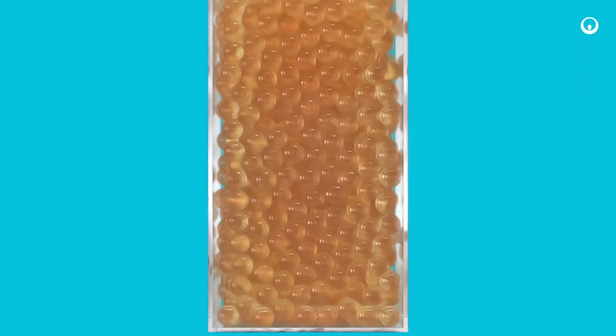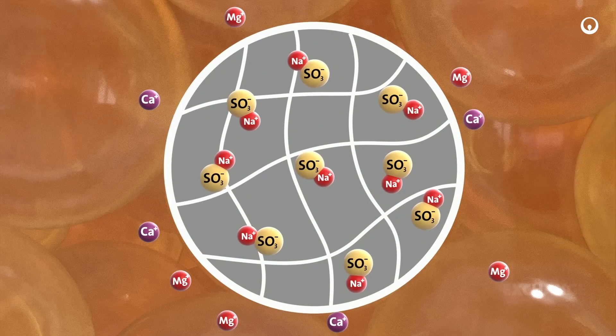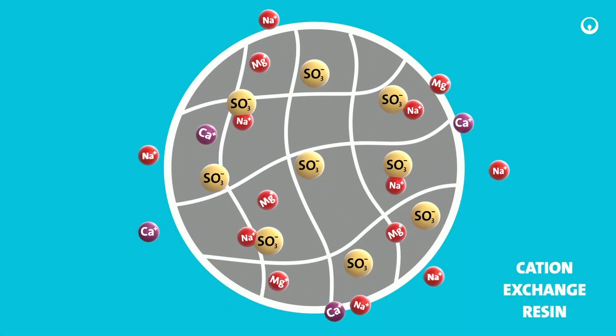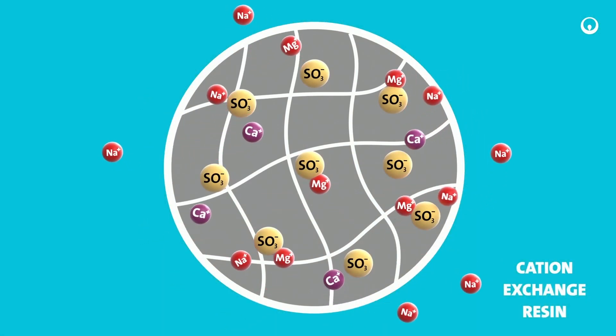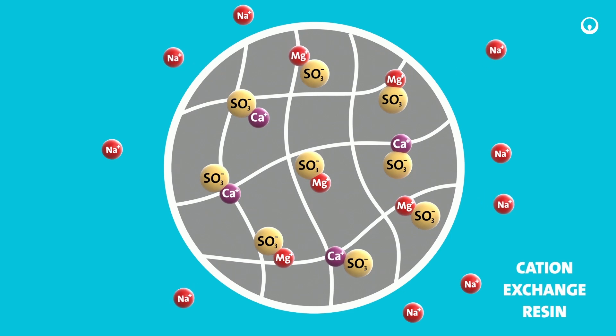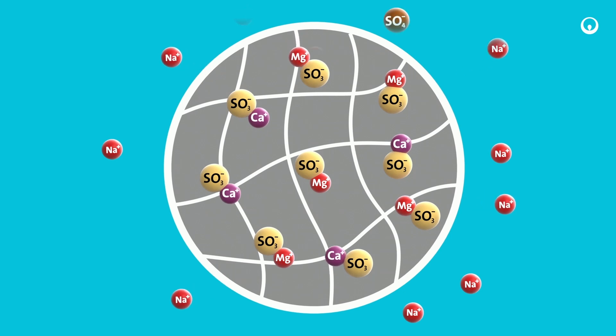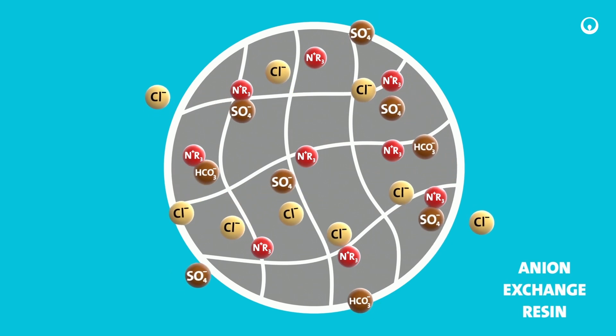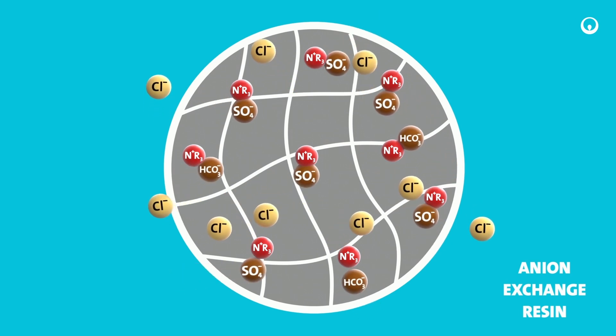An ion exchange resin is a resin or polymer that acts as a medium for ion exchange. Ion exchange can only take place efficiently when the resin has a higher affinity for the mobile ions. Cation exchange resin in sodium form exchanges high-hardness ions into cation resin beads, while anion exchange resin in chloride form replaces sulfate and bicarbonate anions in the water.